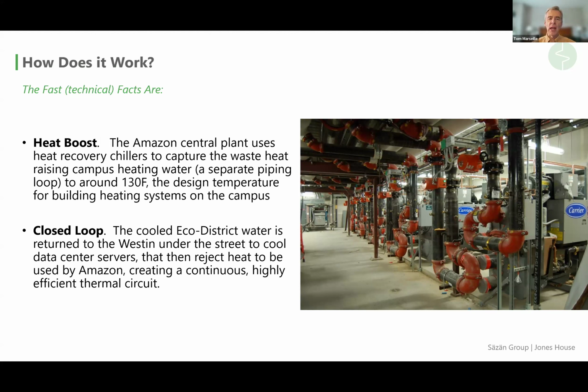But what has to happen when you get to Amazon to make it useful heat is you need what's called heat recovery chillers - you can see those in this photo. They work through a vapor compression refrigeration process, I'm not going to get into the details. They extract heat from that low-grade loop and put it into the heating water loop of the building, which is at 130 degrees, the temperature needed to heat the campus.